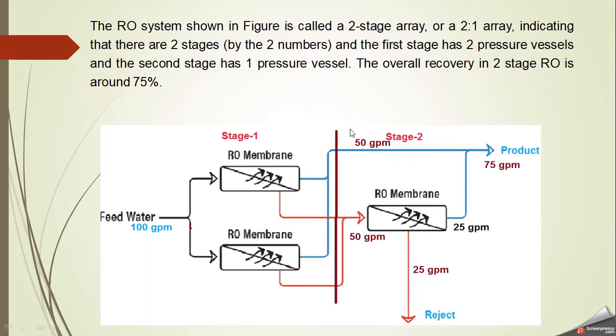Now let's look at what happens with impurities. If 100 GPM of water enters these two membranes and we get 50% recovery, then 50 GPM becomes the permeate product and the remaining 50 GPM concentrate enters the next membrane. With 50% efficiency again, 25 gallons become product and 25 gallons are rejected. So the overall efficiency of this two-stage system is 75%.